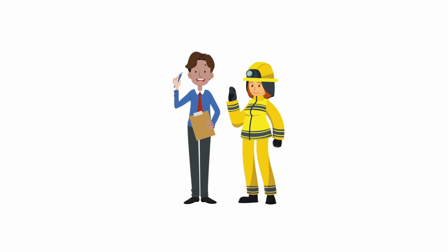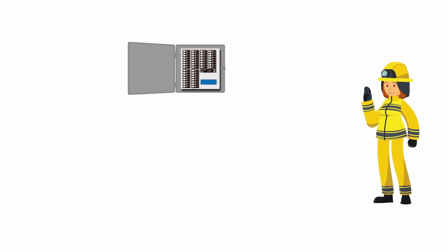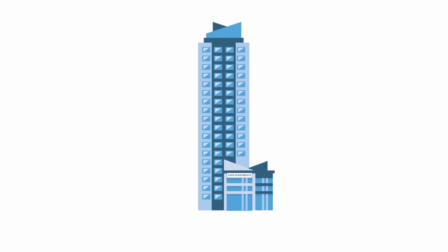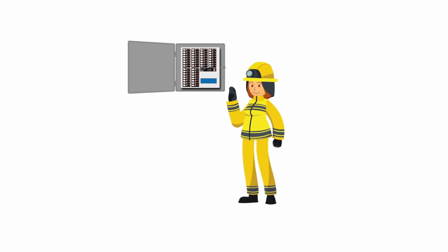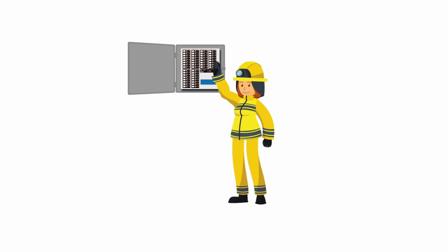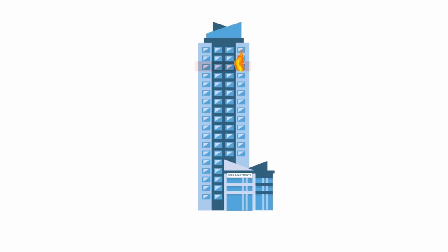After consultation with the relevant fire and rescue services, flats are programmed to belong to building-specific evacuation zones, typically one zone per floor. In an emergency situation, should the fire and rescue service need to evacuate the building, they simply unlock the cabinet and activate the relevant evacuation zone control switch. This will cause all evacuation devices located in that zone to operate.